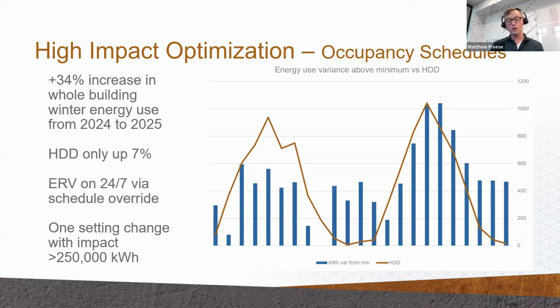And it came down, as it turned out, to a single override for one piece of equipment. Their central ERV for this very large building was put to 24/7 operation for the entire winter. And it meant, even though they had a sophisticated building automation system and a schedule for the equipment that was appropriate and did work for many years, somebody left an override in place for the entire winter, which used about an extra 250,000 kilowatt hours. So that's probably, including demand charge increases, something like a $30,000 touch. So that's an expensive choice that somebody made that nobody knew about, and actually it was undone by the time we got called in to look at something somewhat unrelated, and this kind of popped up in our review of their data.